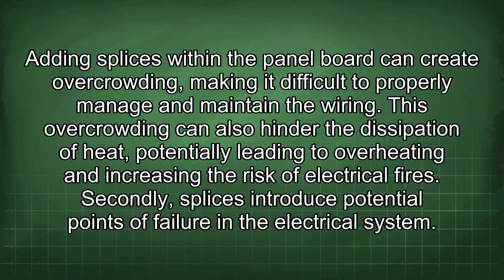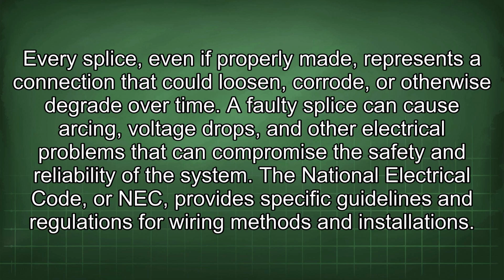Secondly, splices introduce potential points of failure in the electrical system. Every splice, even if properly made, represents a connection that could loosen, corrode, or otherwise degrade over time.